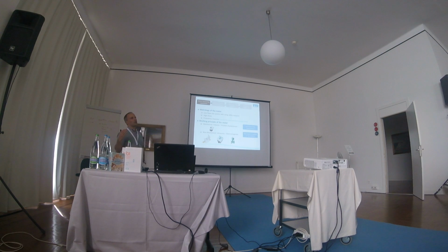So, what we have to worry about is the first thing, the metrology. In most of the studies, if we are thinking about water saving, one of the worst things we can have in a house is leaks. And for example, one thing that has been mentioned in this conference is to use the utility meters. We have to be very careful with that. Why? Because if that meter was installed maybe 4 or 5 years ago, then the starting flow rate of that meter is not low enough, and it is not able to register the leaks inside the house.